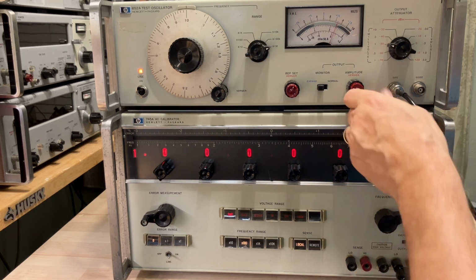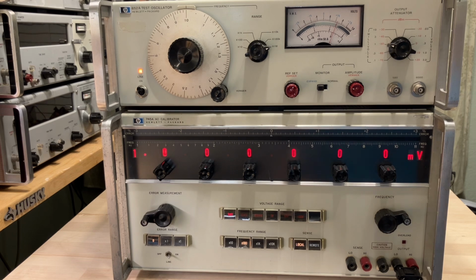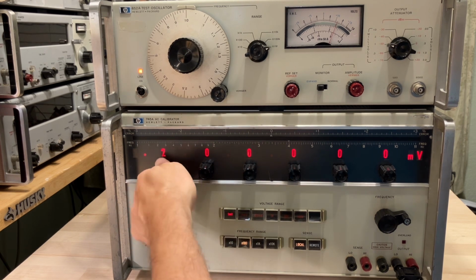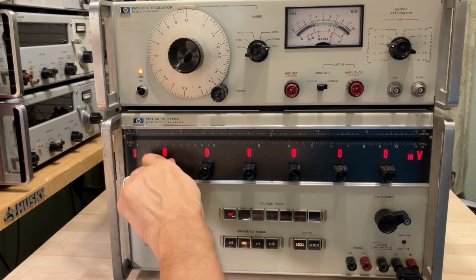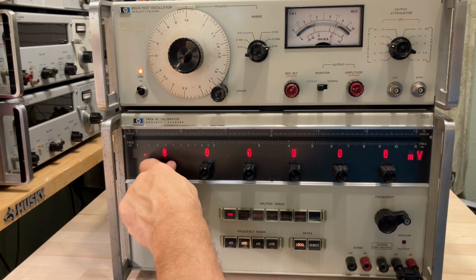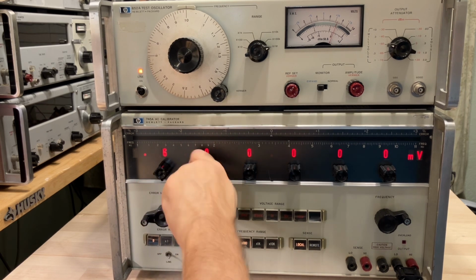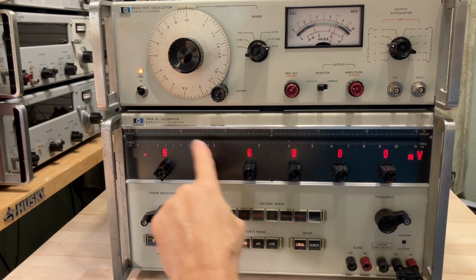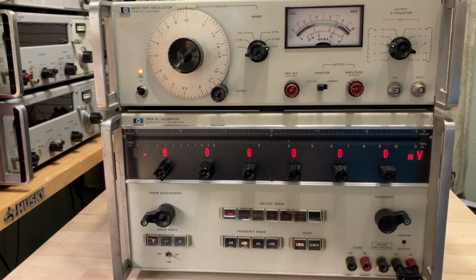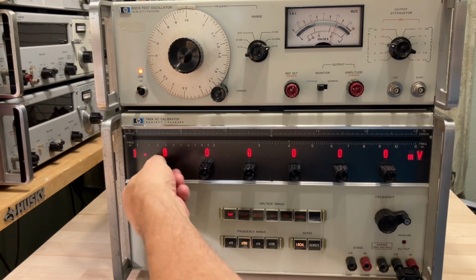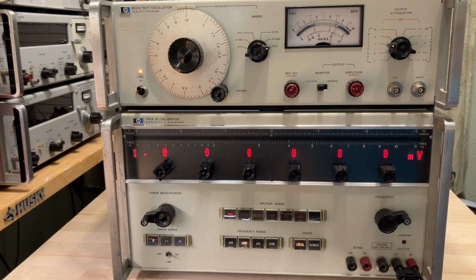I can also use the 745A to test the linearity and tracking of the meter movement of the 400H itself by dialing down this output. So I can go 1 millivolt, 900 microvolts, 800, 700, 600, etc. So this has 1, 2, 3, 4, 5, 6 decades of adjustment. It's an AC voltage standard, and I can use that to test the linearity of my unit under test.